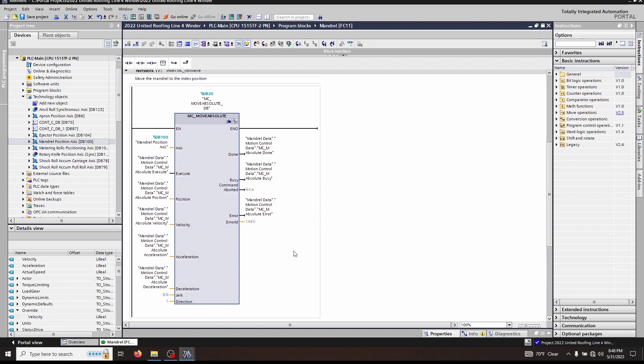In order to do this, the axis has to know where it is, meaning it has to be homed. In a previous episode we talked about the MC_MoveRelative. The MC_MoveRelative did not have to be homed in order to execute. The MC_MoveAbsolute that we're talking about today must be homed first.